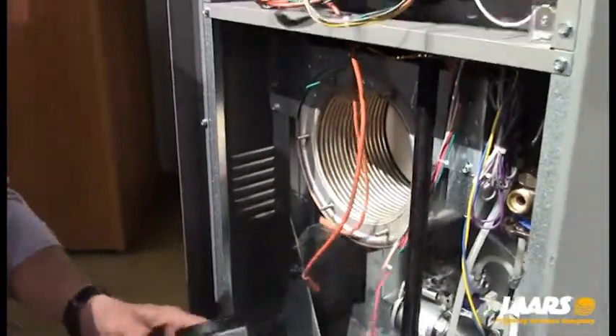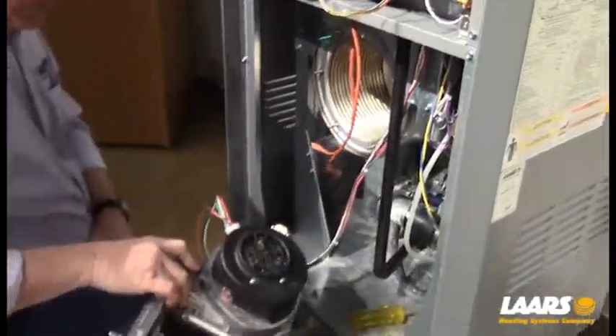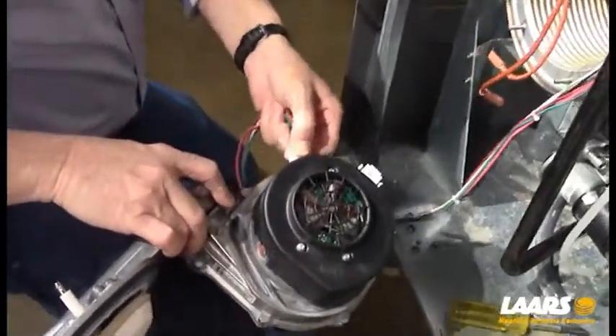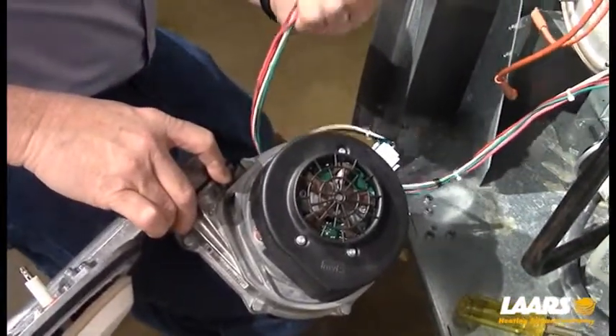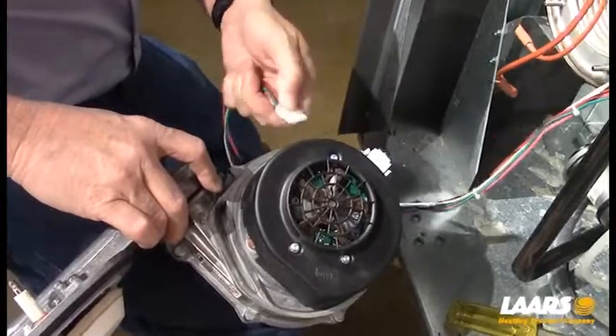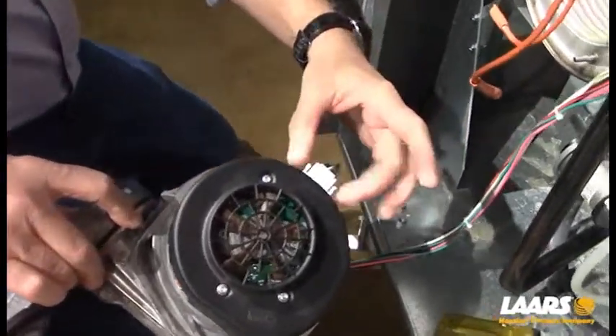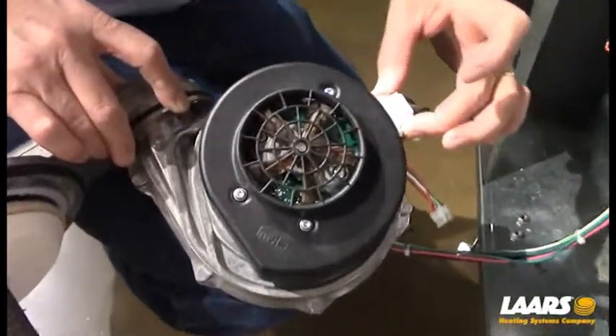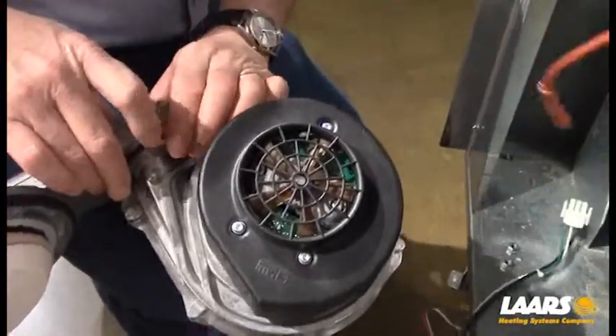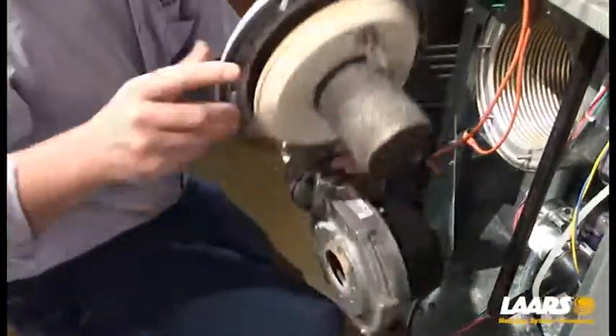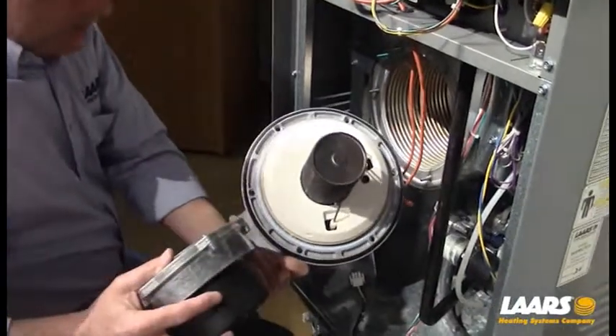And lastly, we need to remove the 2 Molex plugs for the blower. There's our DC signal. There's a little tab on the back side of it. You're just going to pinch on the tab, slide it out of position. And the line voltage, 2 tabs on the side, loosen them and take them out. Now we have the whole burner head and burner complete.